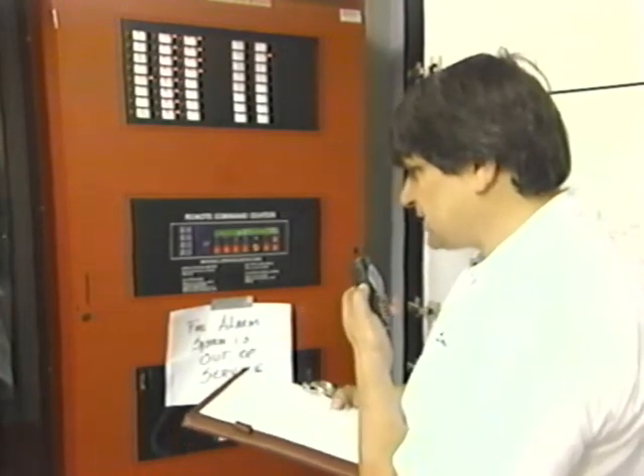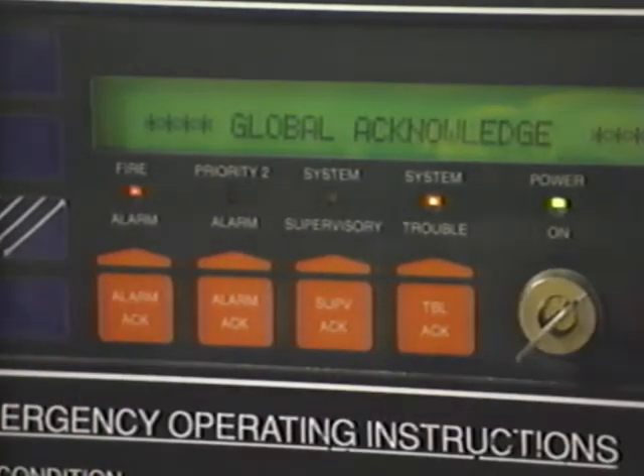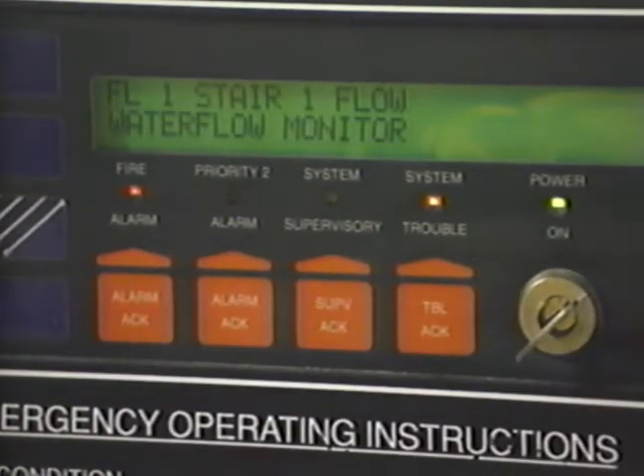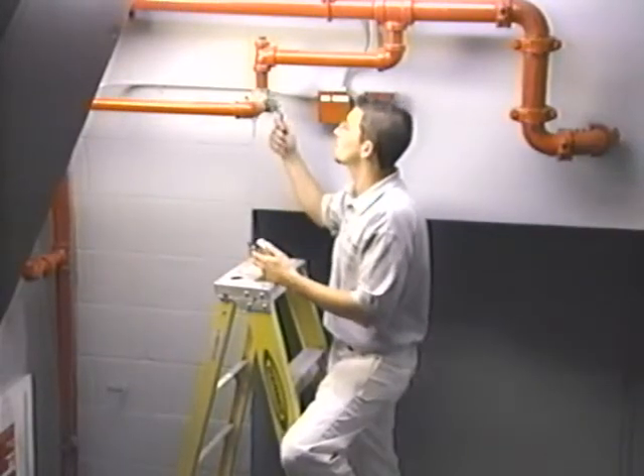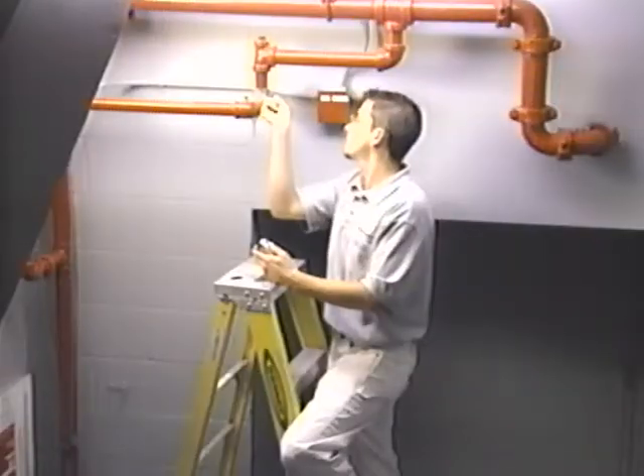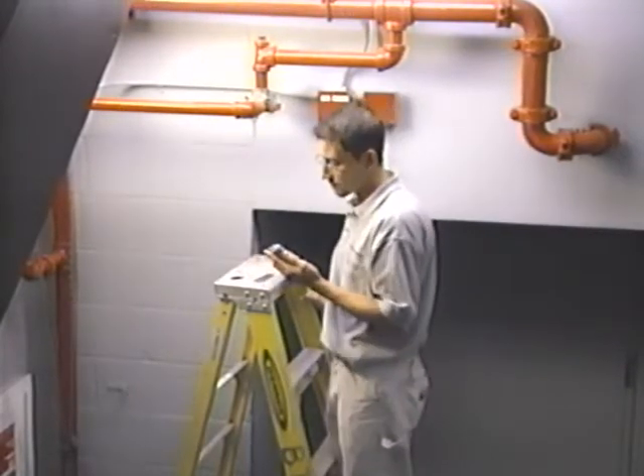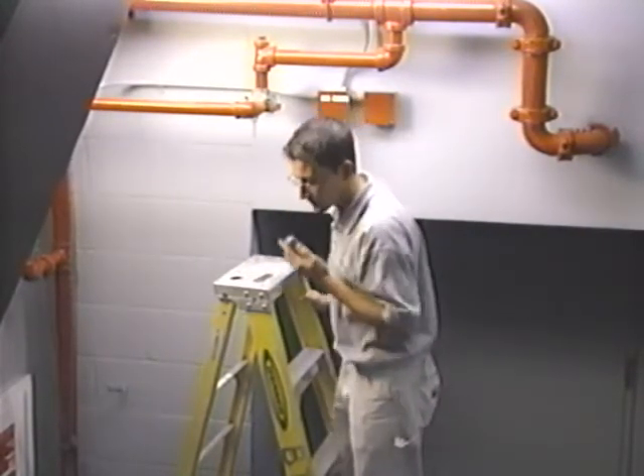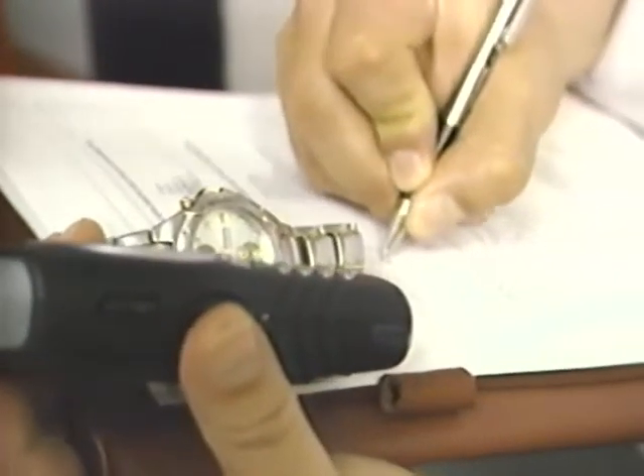Flow water through an inspector's test connection for wet pipe systems and verify receipt of alarm at the control panel — during a demonstration test, the alarm was received in 47 seconds. Make sure the water flows long enough to activate the switches in all parts of the affected system, such as a stand pipe, main flow pipe, or fire pump. Record the time it takes for each switch to activate. If the signal doesn't transmit within 90 seconds, adjustments are needed.